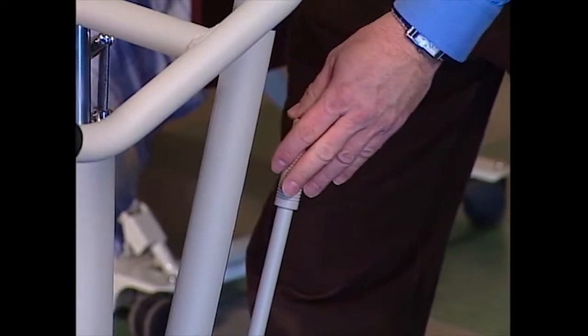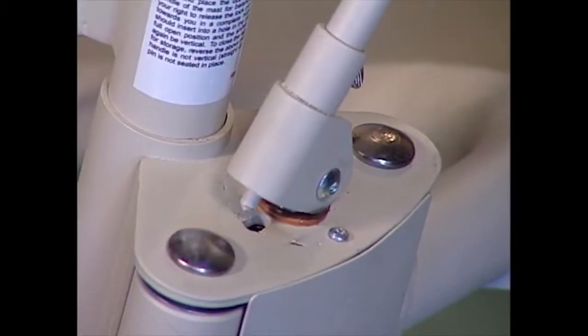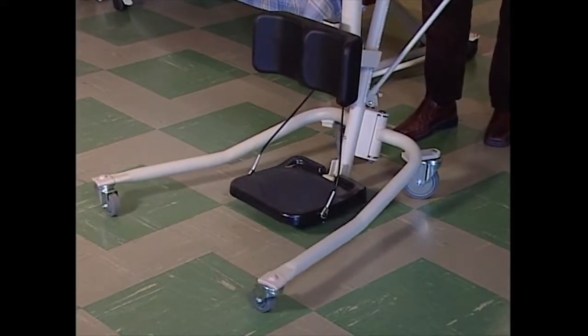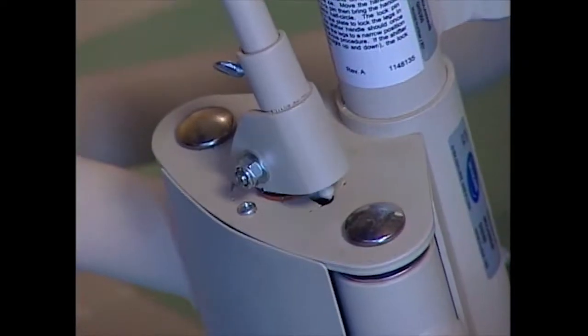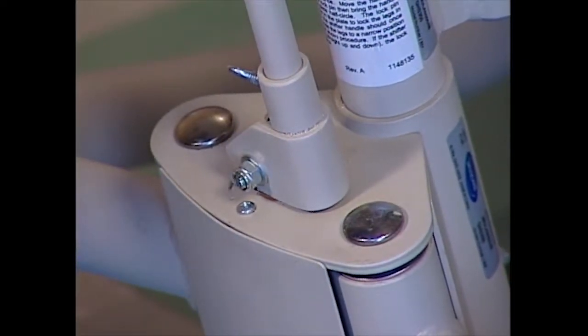Push the shifter handle to your right to lift the locking pin from the closed nesting position on the base. Turn the handle clockwise until the locking pin drops into the open nesting position — when this happens, the legs are open and locked. Make sure that the locking pin is properly nested. It's very important that the legs be fully opened when lifting a resident; if they're not, the lift won't achieve proper weight distribution and balance, and that can result in injury.